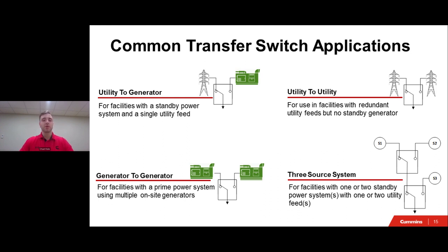This is where you have two generators being connected by an automatic transfer switch. As you can see in that graphic, now instead of having that utility piece off to the left, you just have two generators and your automatic transfer switch monitoring the power between the two, and then also transferring the power between the two generators if needed.